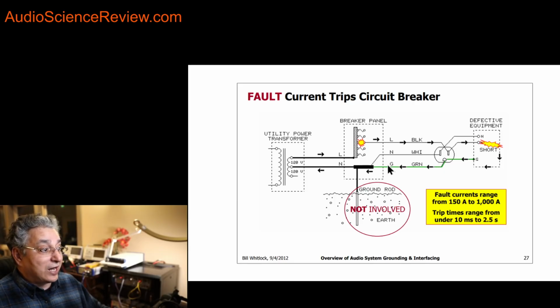So the key is that now the ground wire becomes completing the circuit in here, not the neutral wire, and that is why it's there. It's a form of redundancy, and it's for safety. Notice what Bill has circled in here. The fact that this was hooked up to the ground, to dirt outside, there was this ground rod that went to the earth outside, has absolutely nothing to do with this path, right? This path was here from the ground, going in here, boom, and the breaker broke. Nothing went down to dirt.